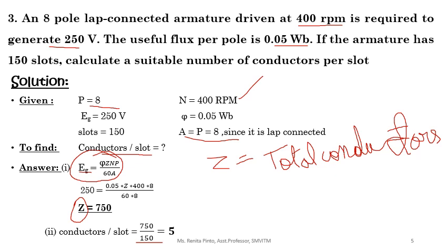Generated voltage EG is given. Phi is given. Z is the total number of conductors — that is what I need to calculate first, and then further calculate conductors per slot. N and P are given; 60 is a constant. Since it is lap connected, A equals P equals 8, so P and A cancel. Calculating this, you get the total number of conductors; then divide by 150 slots to get conductors per slot.